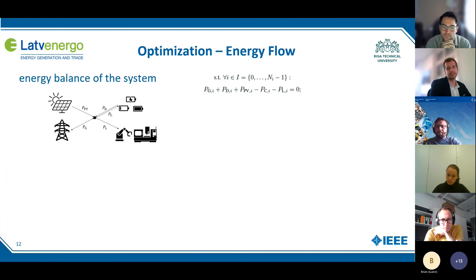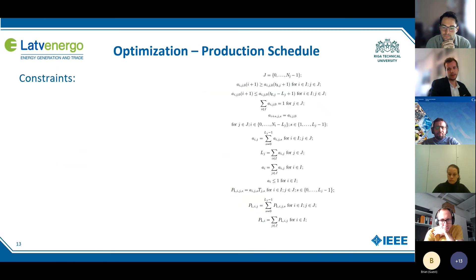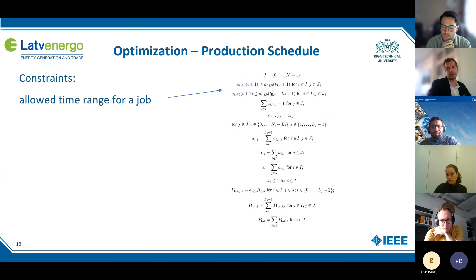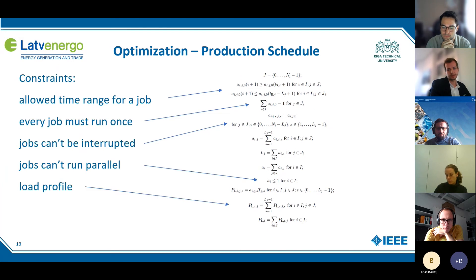For the energy flow optimization, we can use the energy balance of the system shown before and the energy balance of the battery model as constraints. The last part of the optimization is the production scheduling. The constraints allow a time range for every job, so every job has a start date and a finish date. Every job must run once and jobs can't be interrupted once started. Also, jobs can't run in parallel, and at the end we calculate the resulting load profile from the digital twin estimations for every job.